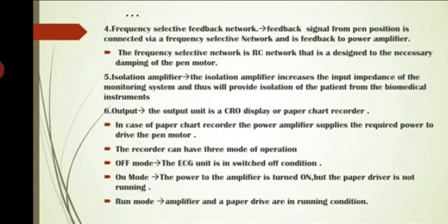Fourth, frequency selective feedback network. Feedback signals from the pen position are connected via a frequency selective network and fed back to the power amplifier. The frequency selective network is an RC network that is designed to do the necessary damping of the pen motor.